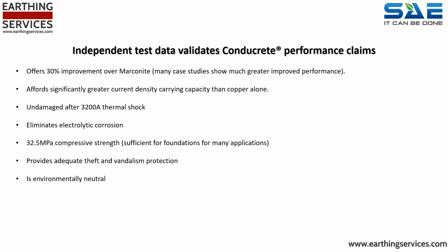It affords significantly greater current density carrying capacity than copper alone, is undamaged after 3,200 amp thermal shock, eliminates electrolytic corrosion, has a 32.5 MPa compressive strength on average, provides adequate theft and vandalism protection, and it is environmentally neutral.